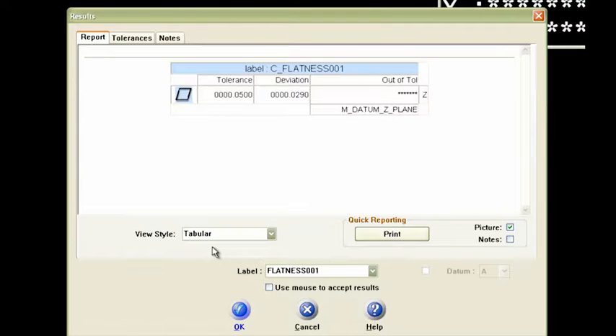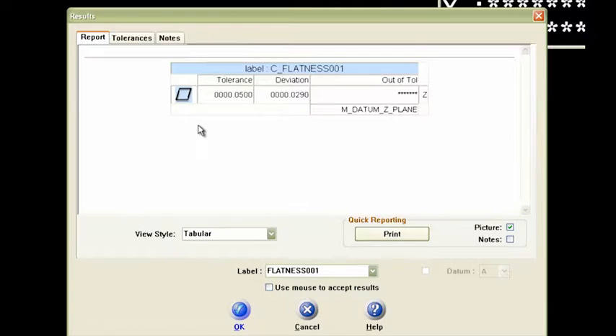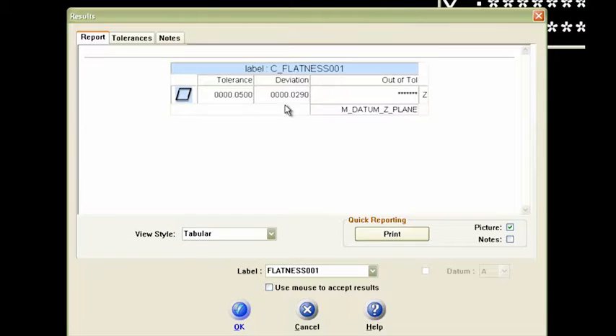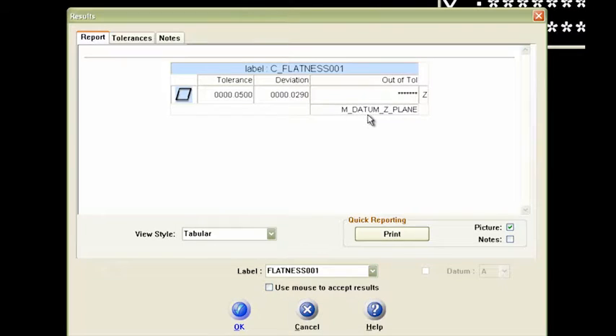what I've got is this dialog box that comes up here for the results. I've got the tolerance at 50 microns. Here's the deviation from those 12 points. I had 29 microns, so I don't have anything out of tolerance. And what it's saying is that the datum Z plane is what we tested for this flatness.